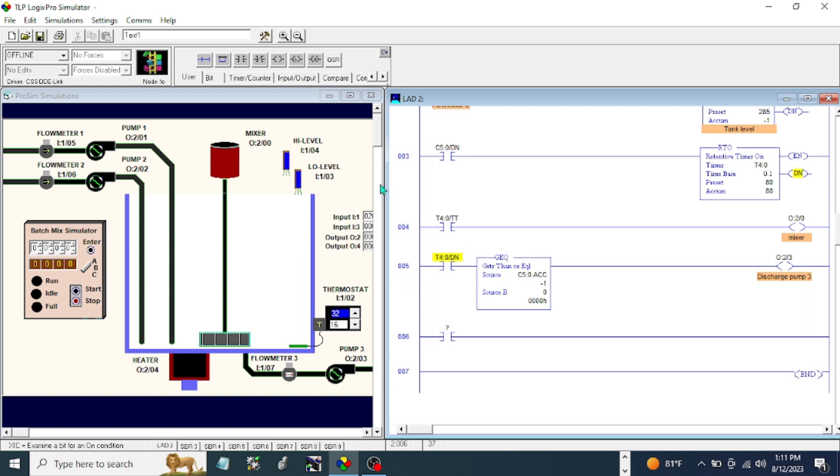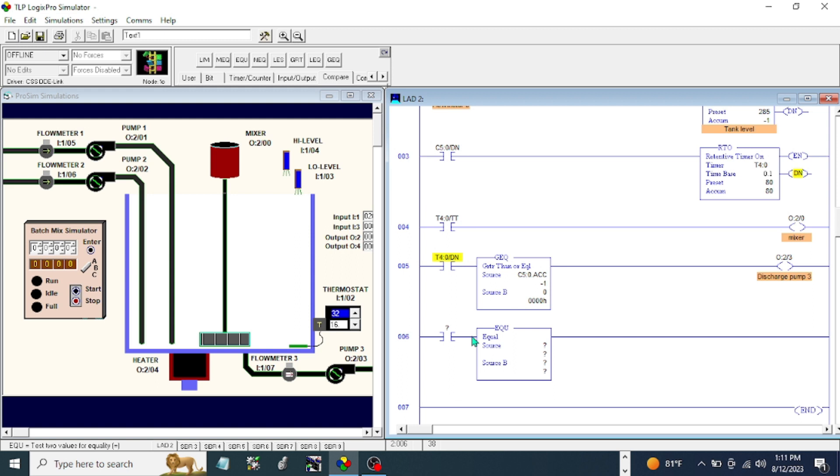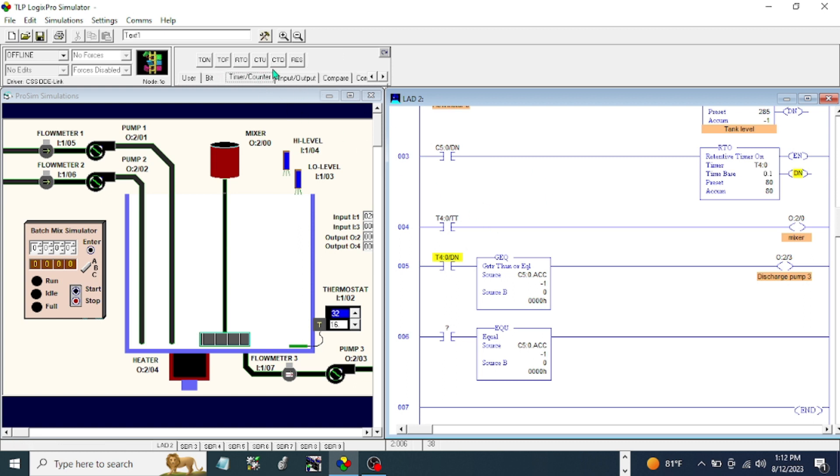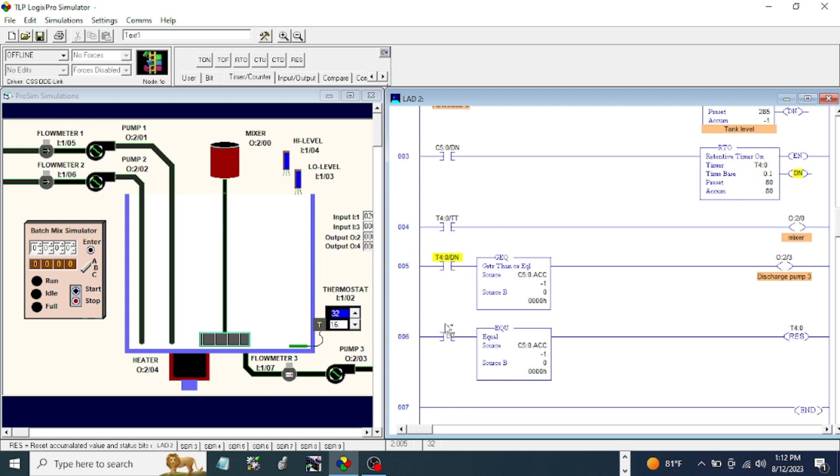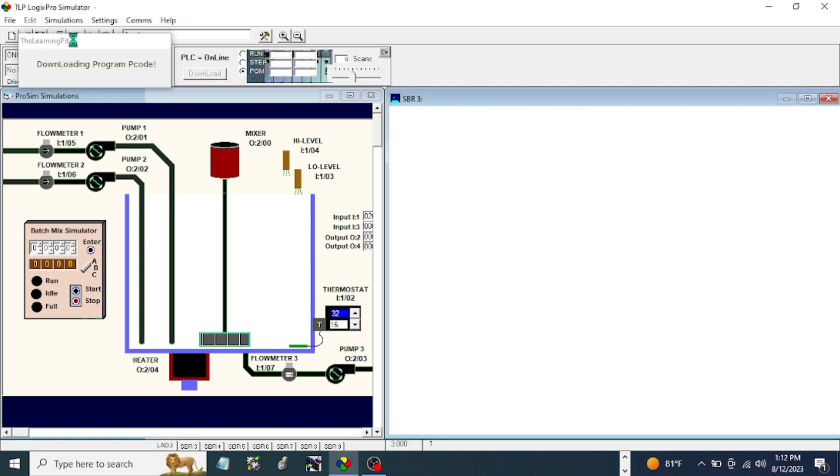We need another compare instruction again. I will just do equal. And I will use source A is equal to zero and it will reset our timer. And the address is our retentive timer. Okay, and let's try to do done bit here if it's going to work. This is just like trial and error. Let's download it.